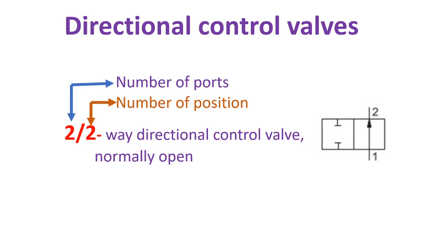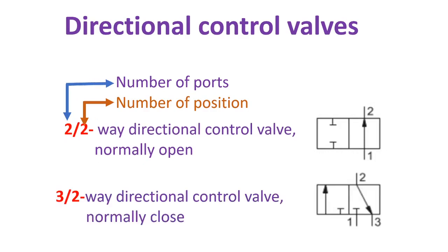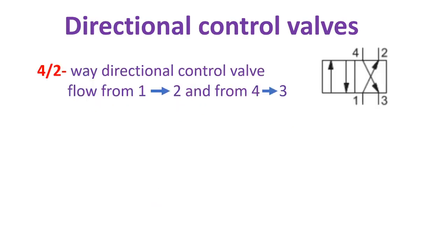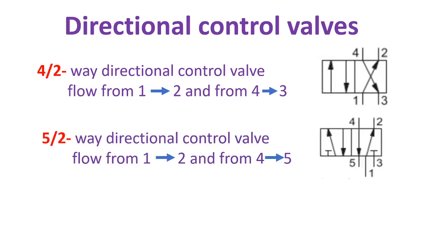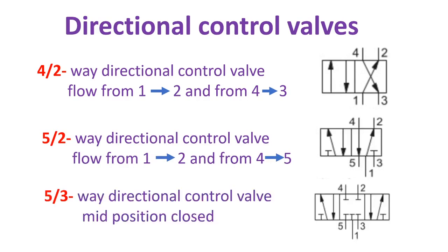This valve is a two-two-way directional control valve, normally open. The next one is a three-two-way directional control valve, normally closed. The next is a four-two-way, flow from 1 to 2 and from 4 to 3. Then a five-two-way, flow from 1 to 2 and from 4 to 5. Next, a five-three-way directional control valve, mid position closed.